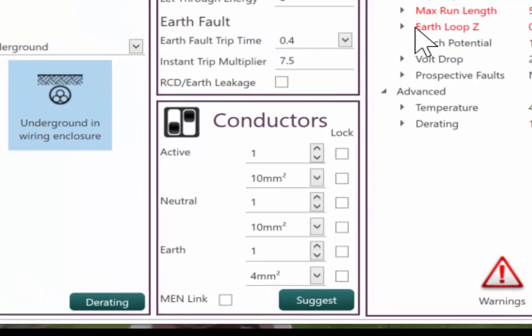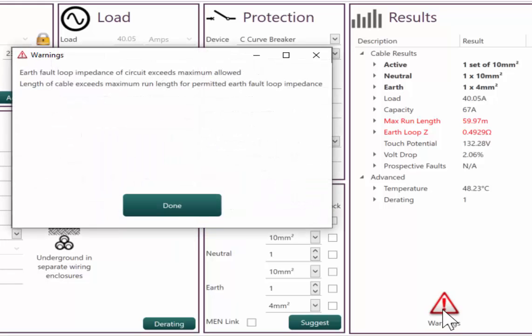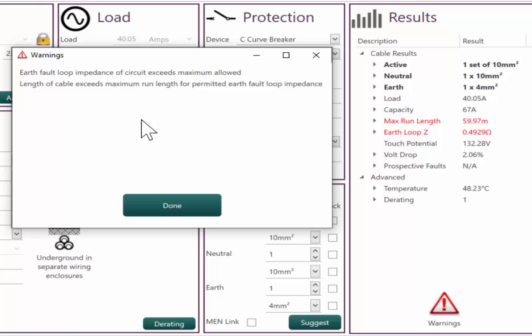But we have immediate, we have a warning over here. So the warning is to click on the warning button. Earth fault loop exceeds maximum allowed. And the length of cable exceeds.